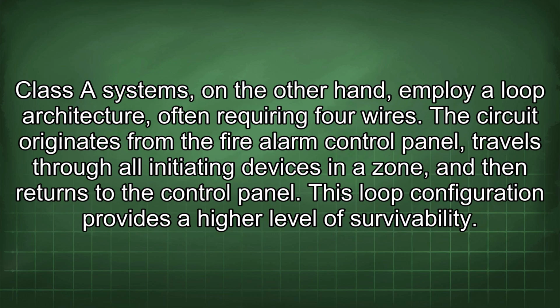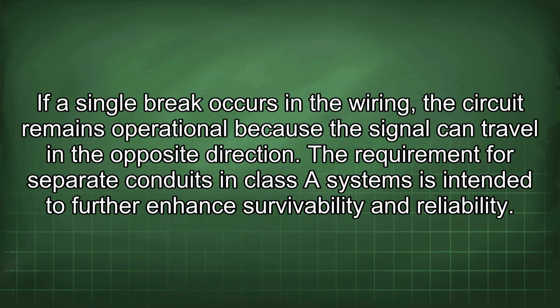Class A systems, on the other hand, employ a loop architecture, often requiring 4 wires. The circuit originates from the fire alarm control panel, travels through all initiating devices in a zone, and then returns to the control panel. This loop configuration provides a higher level of survivability. If a single break occurs in the wiring, the circuit remains operational because the signal can travel in the opposite direction. The requirement for separate conduits in Class A systems is intended to further enhance survivability and reliability.